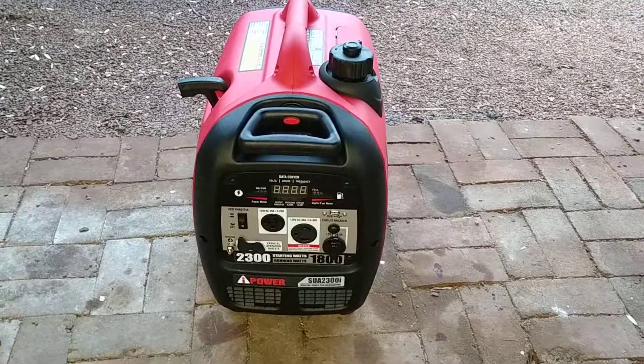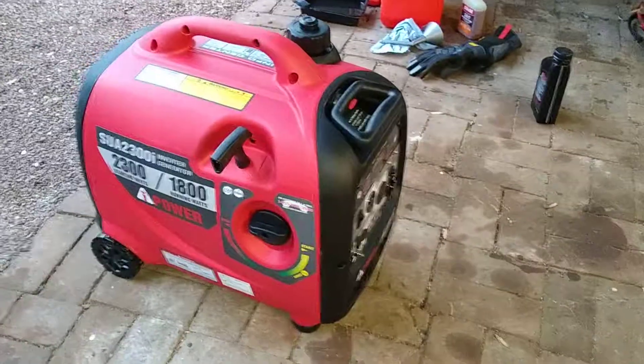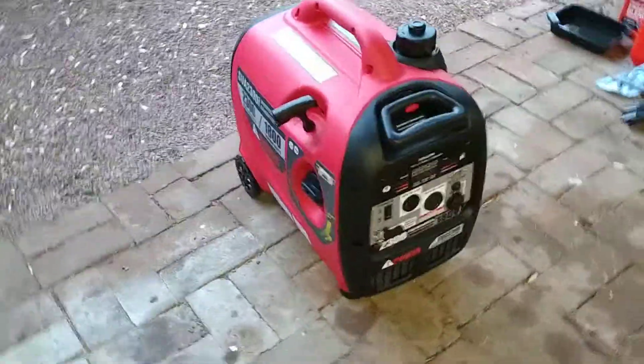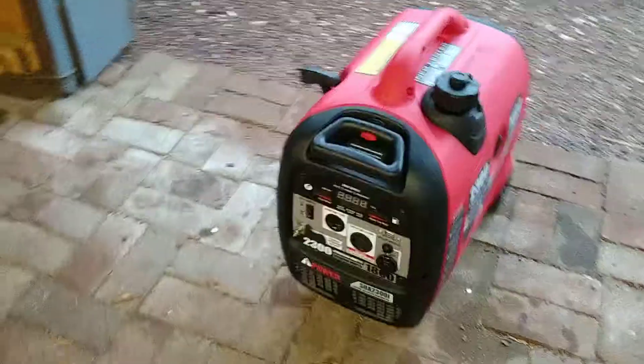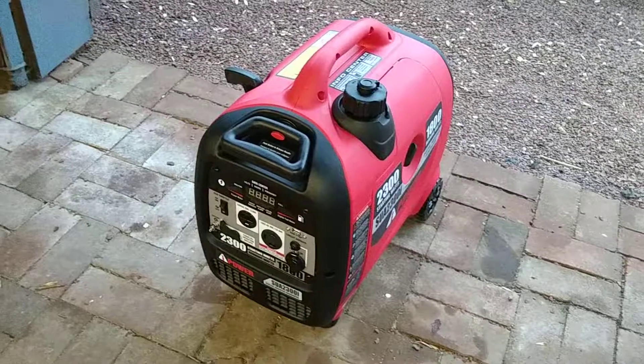Quick update on the A-iPower SUA2300i Inverter Generator. I had the chance to run it through a full tank of gas. It's a 1.1 gallon capacity — I had about a gallon in there — with a 1,500 watt heater connected to it for most of that time, and it ran about four hours on the gallon of gas. So that's pretty good.